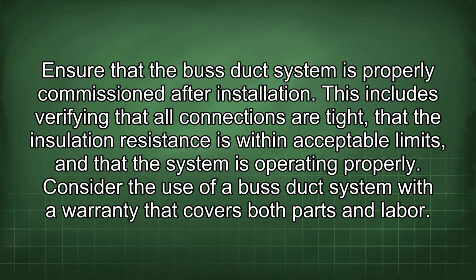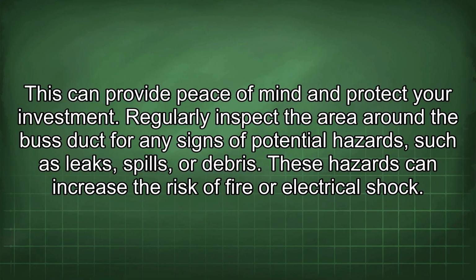Ensure that the bus duct system is properly commissioned after installation. This includes verifying that all connections are tight, that the insulation resistance is within acceptable limits, and that the system is operating properly. Consider the use of a bus duct system with a warranty that covers both parts and labor. This can provide peace of mind and protect your investment.